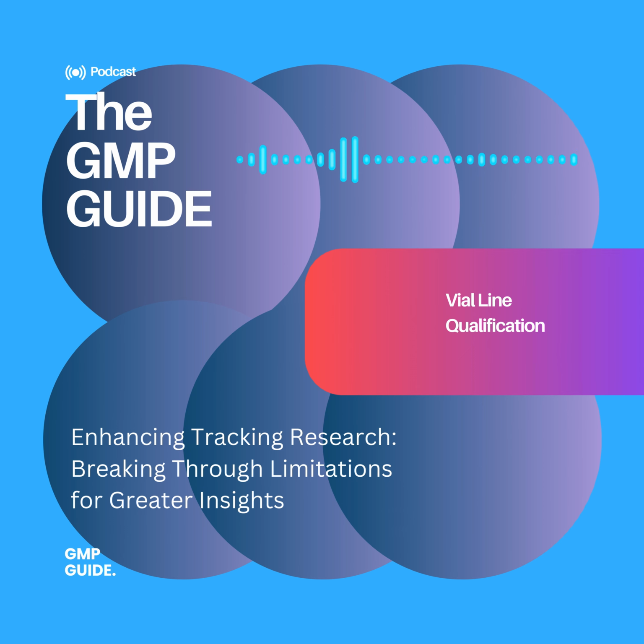Seriously, it happens. It also covers verifying environmental and operating conditions, such as ensuring a clean room maintains its specific temperature range, as well as the correct software system installation, accessibility, and robust connections with peripheral units. Finally, recording the calibration and validation dates of any tools used during the IQ process is essential. That traceability is key. What then truly makes an IQ successful? What's the ultimate indicator that this crucial first step has been done correctly?